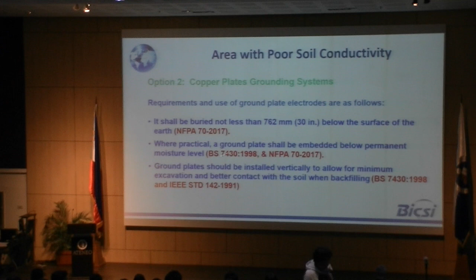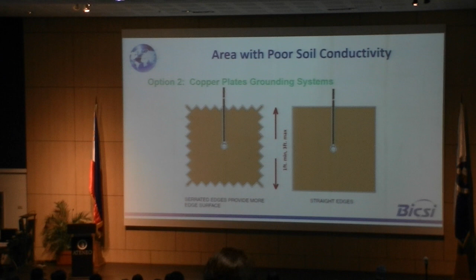Option 2, copper plate grounding systems, which is what we showed. Then these are the standards that comply with it, the compliance requirements for copper systems. This is it, copper plate, and there's also a requirement for the minimum thickness or minimum size. Here, minimum is 1 foot, recommended is 3 feet, and that's how it should be done.